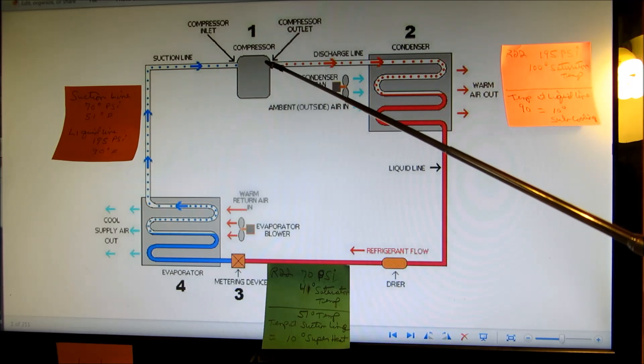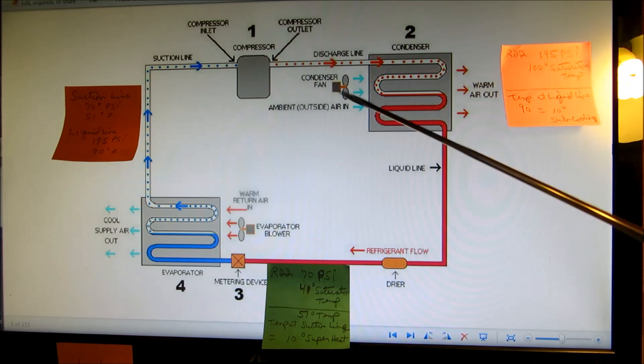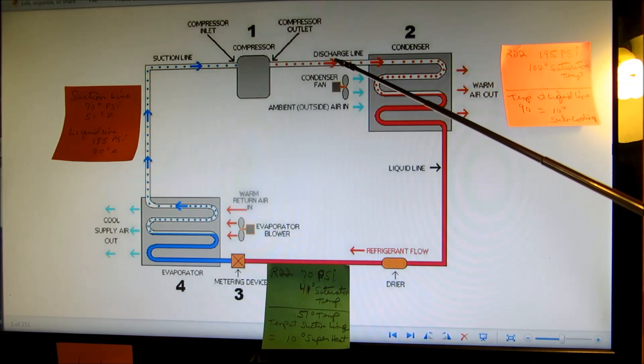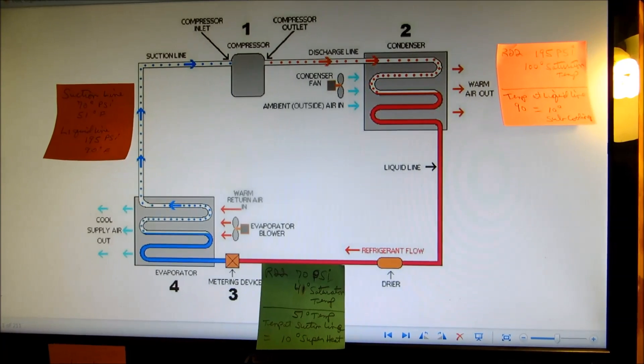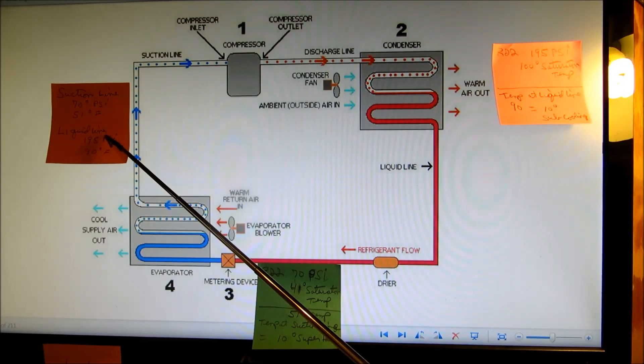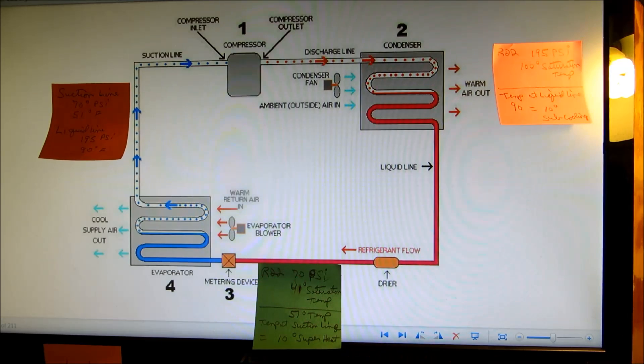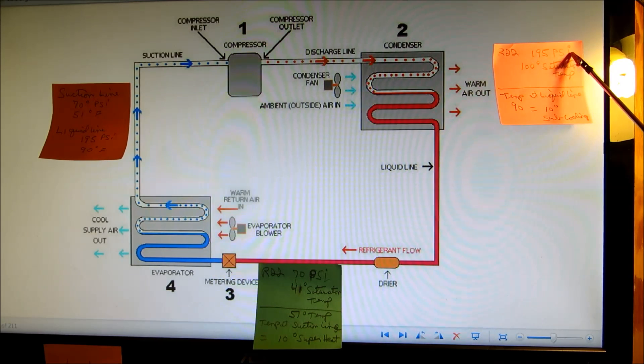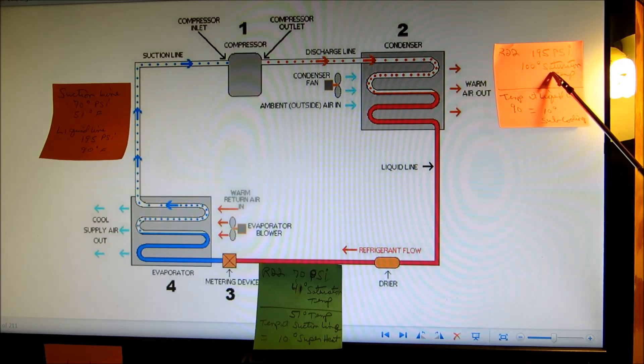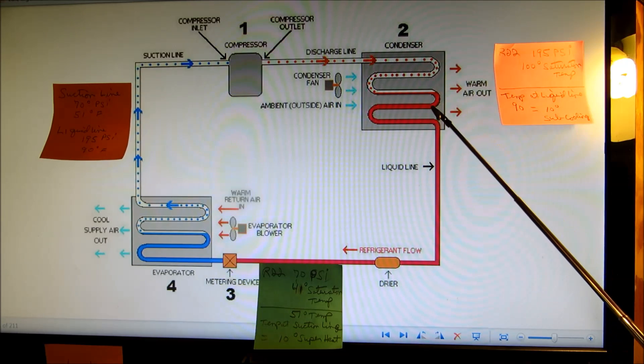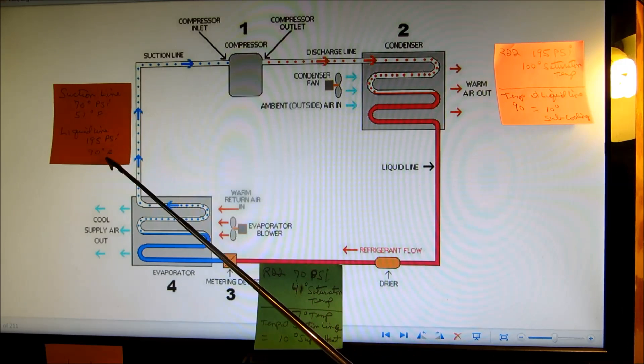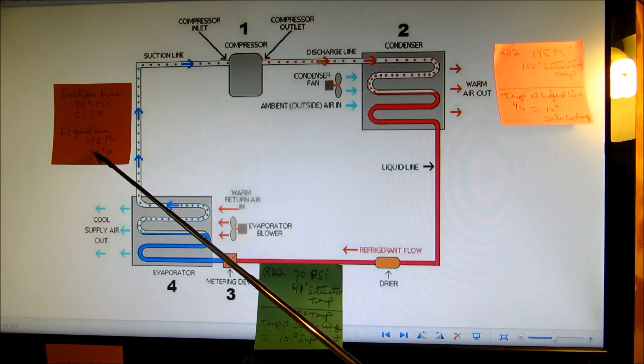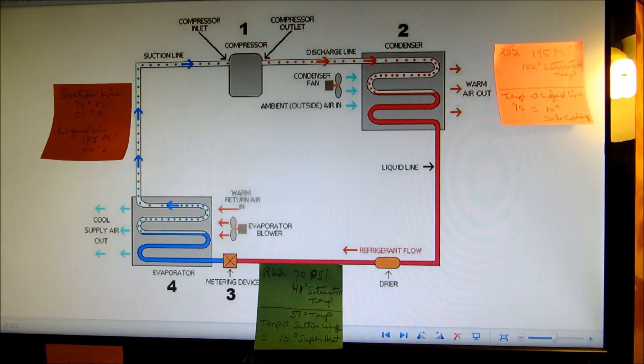As the gas goes through the compressor, it pumps up and the discharge is high-pressure gas. It comes into the condensing unit — hence the name — and the condenser condenses the hot gas into a liquid. The liquid line pressure is 195 PSI; at 195 PSI, R22 saturates at 100 degrees Fahrenheit. That red line inside the condensing unit would read 100 degrees, but we're measuring our liquid line coming out of the condenser and reading 90 degrees Fahrenheit.